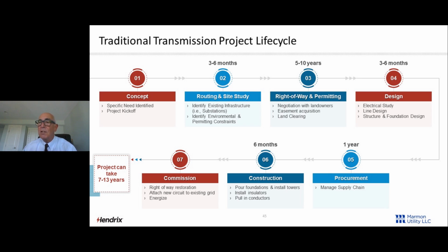Design, maybe 3 to 6 months, 9, 12 months of electrical study, line design, structure and foundation design. We know how to do that. Get down to procurement. Hopefully that's going to take 6 months. We put 1 year here. Construction, we put 6 months. Might be 6 months, might be a little bit longer, depending upon how big the line is. Pour foundations, install towers, install conductors, etc. And then commissioning. So that project for new right-of-way can take 7 years if you're lucky, 7 years if you're darn lucky, more like 13 years.